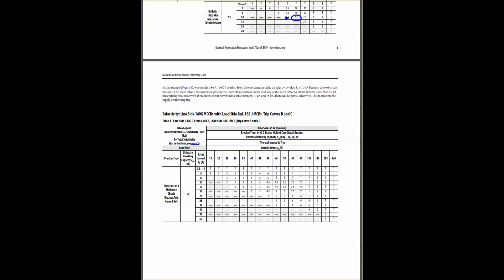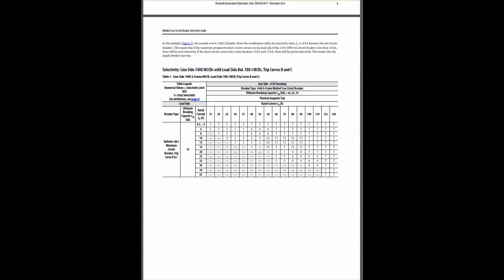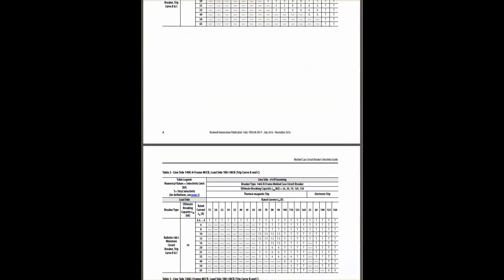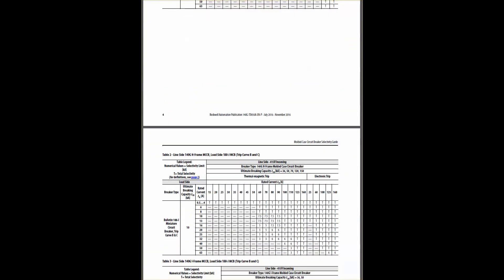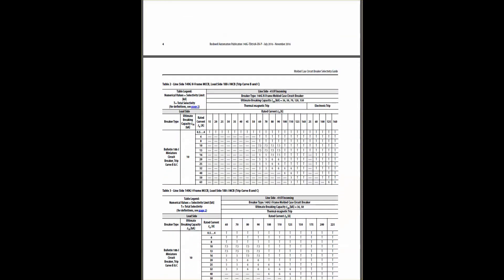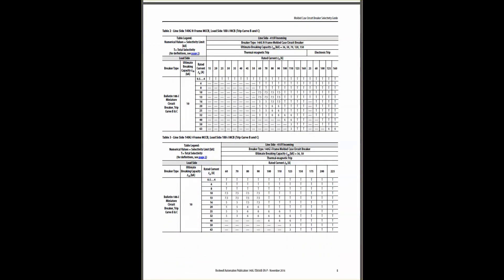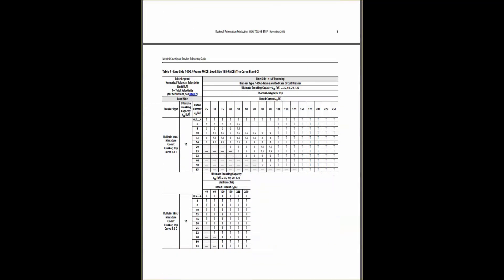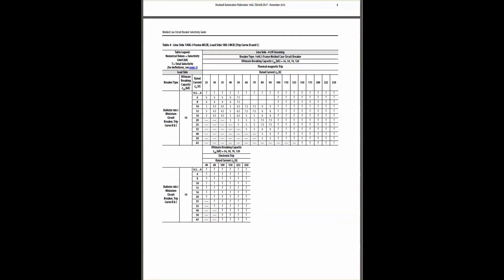When a short circuit fault occurs at the load side, both breakers will see the same fault current. Without selective coordination, both the main and branch circuits will trip. The Selectivity table provides pairs of circuit breakers that fall into two categories: Total Selectivity and Partial Selectivity.